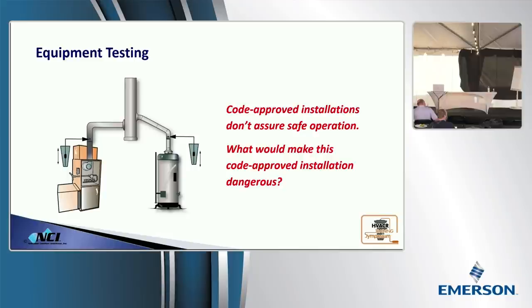Why the pre-purge? Because all gas valves leak, 10% of the lower explosive limits. What happens if the ignition source comes on at the same time the gas valve energizes? Hopefully it'll light. You're warmer quicker. What happens if the gas valve comes on before the ignition source? Things go boom. It's bad when things go boom. So just in case there's any residual fuel in here, the inducer is going to pre-purge, clear all that out, verify that the flue is opening or open, unless it's on this installation, and then it will allow the sequence of heating operation to continue.